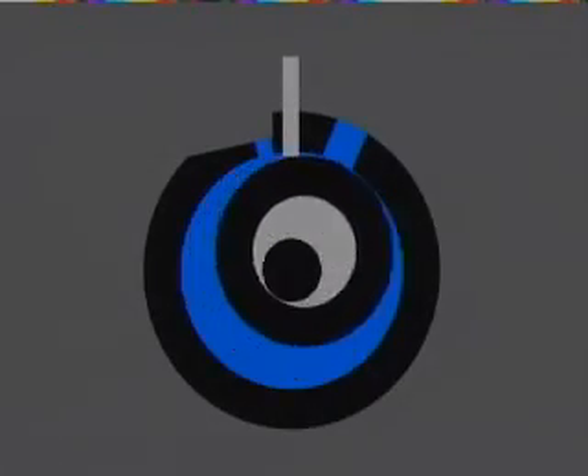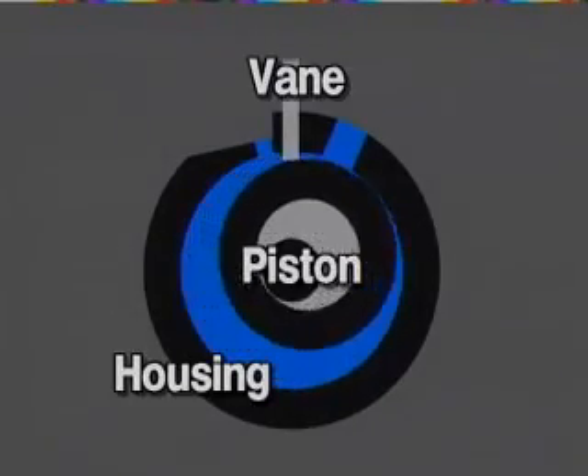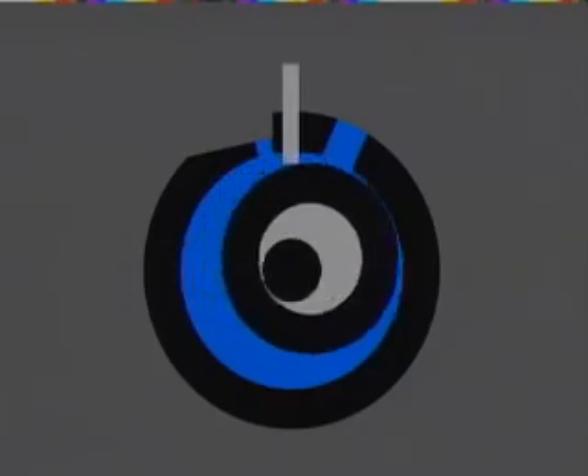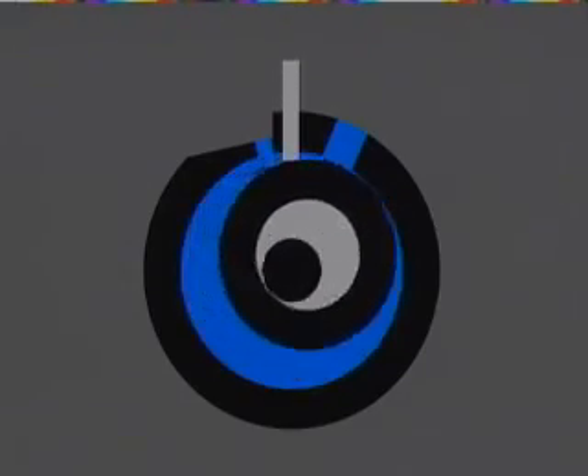A rotary compressor uses a rolling piston within a cylindrical housing to compress vapor against a reciprocating vane. The spring above the vane holds it in contact with the rolling piston at all times, providing a vapor-tight seal between the high and low pressure zones within the compressor.